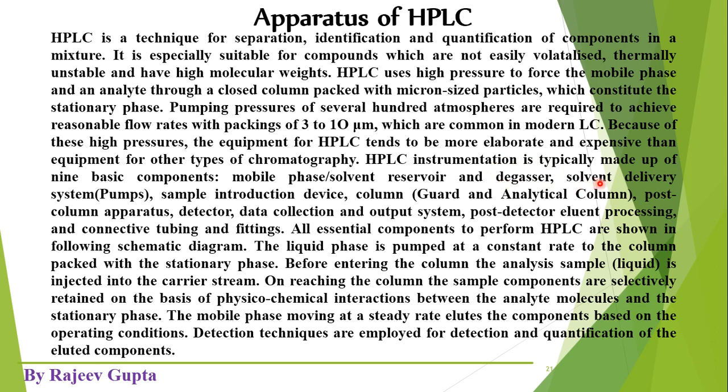Now the second point is solvent delivery system or pumps. These are a very highly required part of this HPLC, where these pumps push the mobile phase or solvent at very high pressure inside the instrument. So using these very high pressurized pumps, we apply very high pressures of several hundred atmospheres. So at these high pressures, the liquid flows through the very fine and completely close packed columns.